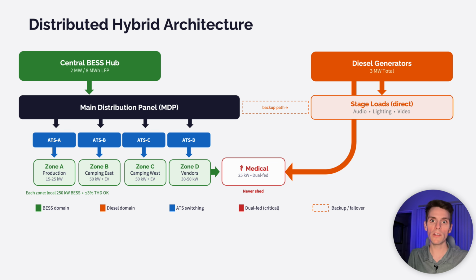The distributed architecture places a central BESS hub and local battery units near load centers throughout the festival grounds and site. Production, camping zones, and vendors, while diesel generators directly supply stage audio, lighting, and video. Automatic transfer switches, shown as ATS, provide failover at every site. Medical facilities get dual-fed power from both sources, never shed. The topology provides N+1 redundancy, reduced cable runs, and a very flexible deployment.